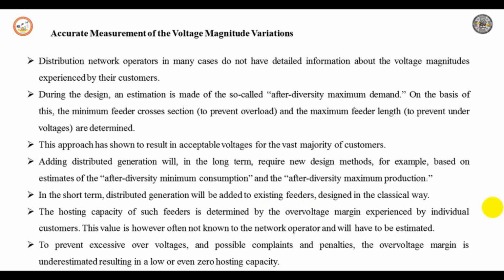Distribution network operators in many cases do not have detailed information about the voltage magnitudes experienced by their customers. During the design, an estimation is made of the after-diversity maximum demand. On the basis of this, a minimum feeder cross section and maximum feeder length are determined. This approach has resulted in acceptable voltage for various customers. Adding distributed generation will in the long term require a new design method, for example one based on estimation of the after-diversity minimum consumption and after-diversity maximum production. In the short term, distributed generation will be added to existing feeders designed in the classical way.